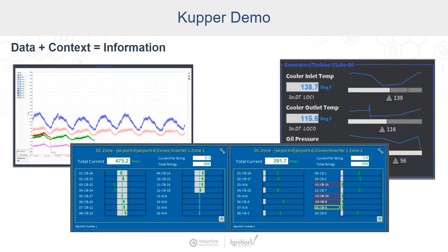It's also incredibly helpful to show context along with the data to provide useful information. This might mean using a pre-built set of trends to allow comparison of related data, like seen on the top left. On the top right, we're using a numerical display which provides a tag name, detail about where the data is coming from, the engineering units, and a sparkline of what the measurement has been doing for the last few hours, and an analog indicator showing how far away we are from a problem.